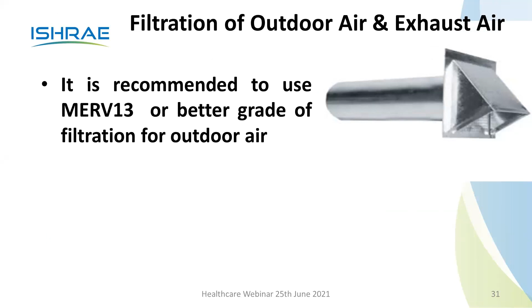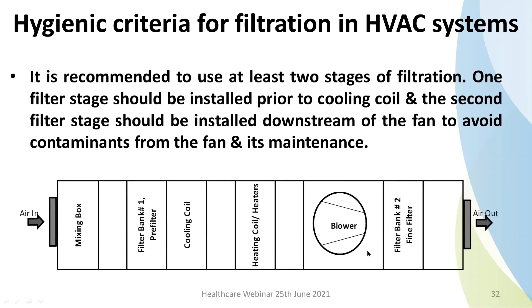Then hygienic criteria for filtration: it is recommended to use at least 2 stages of filtration. One filter stage should be installed prior to the cooling coil, and the second filter stage should be installed downstream of the fan to avoid contaminants from the fan and its maintenance. So typically you will find it like this. You've got a mixing box, then you've got a filter bank, which is the pre-filter, then cooling coil, then heating coil, then the blower, and then the bank number 2.